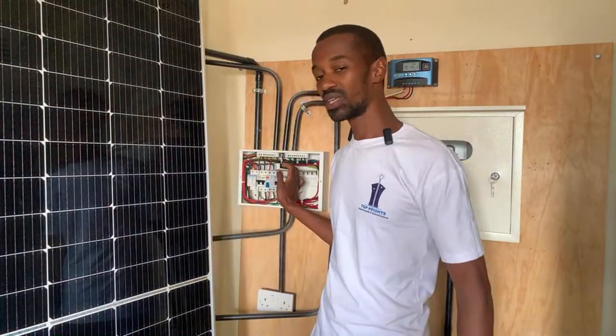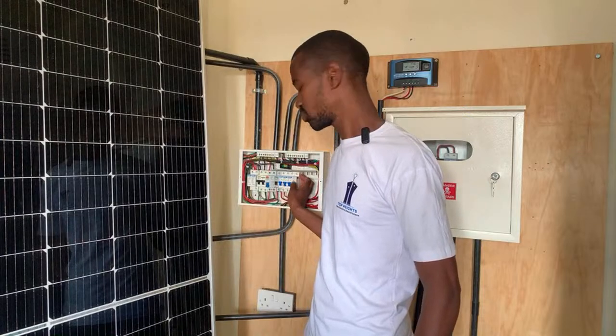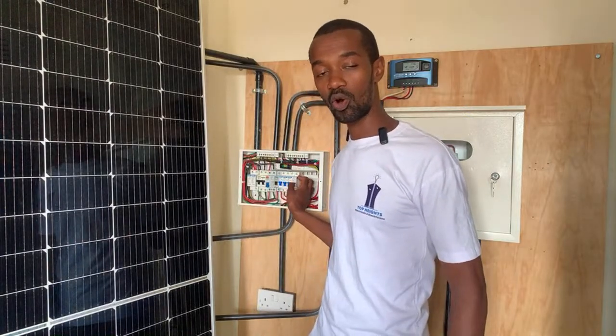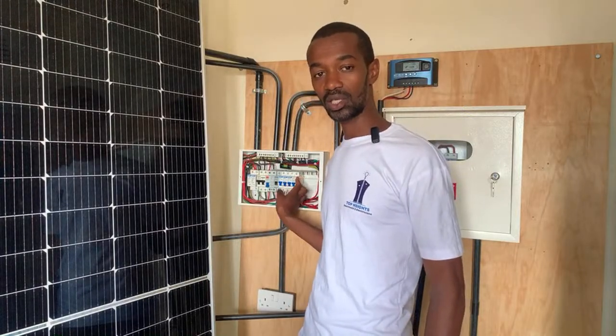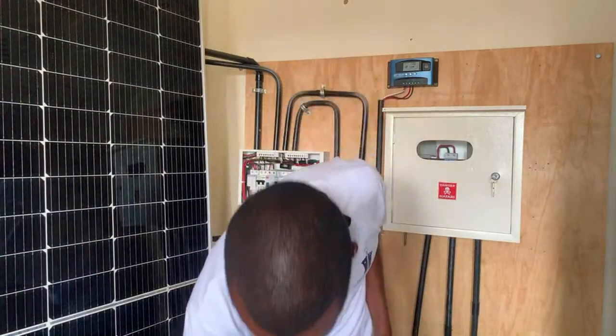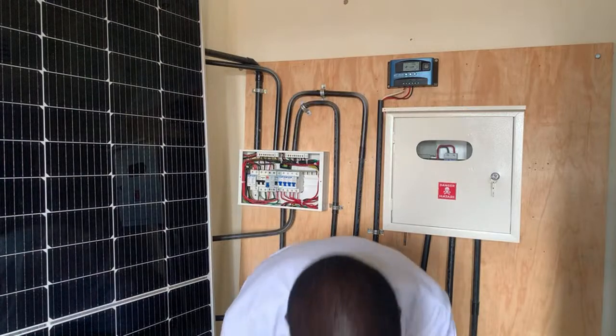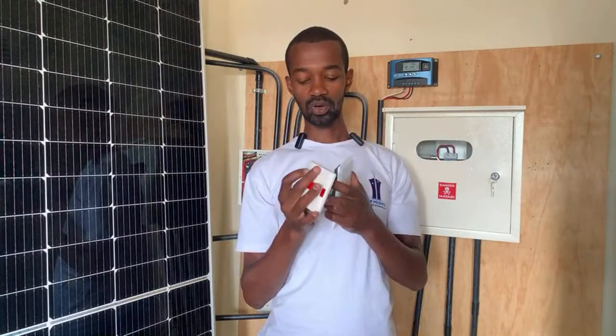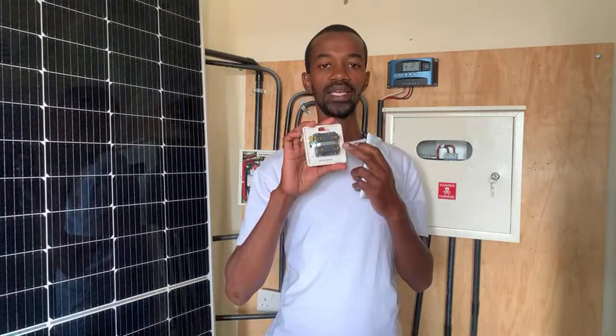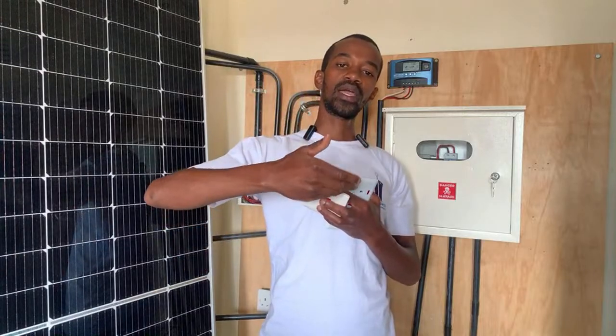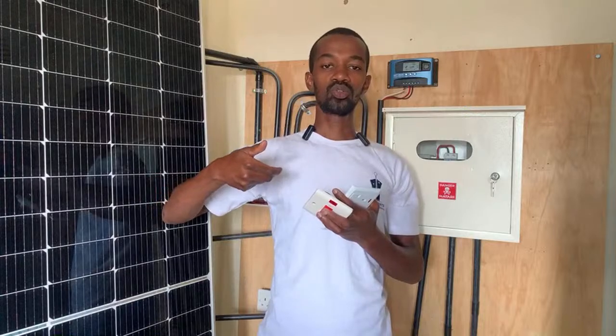When it comes to the consumer unit, which I'll zoom into shortly, another problem on the heating circuit is if there is a loose connection at the consumer unit or at the fixtures - the switches and sockets. Loose connections at a socket will cause overheating at the fixture itself. At a switch, a loose connection will definitely overheat, because electricity must come in through the phase, and for the circuit to be completed, it has to go back to the source, the transformer.